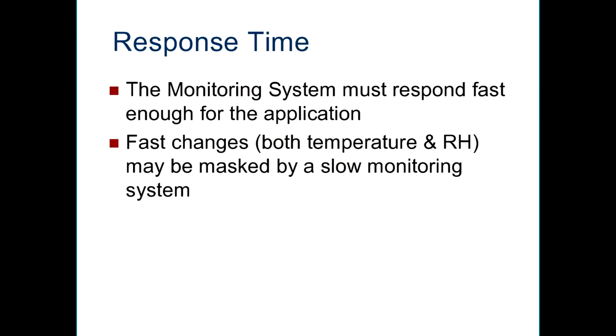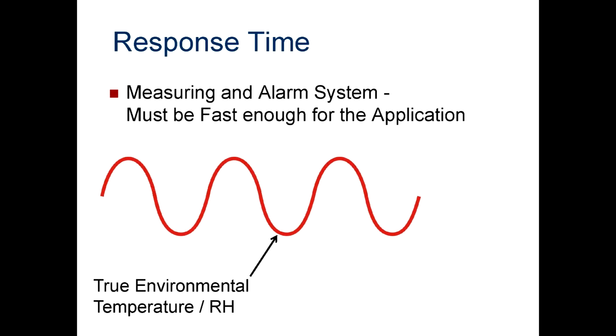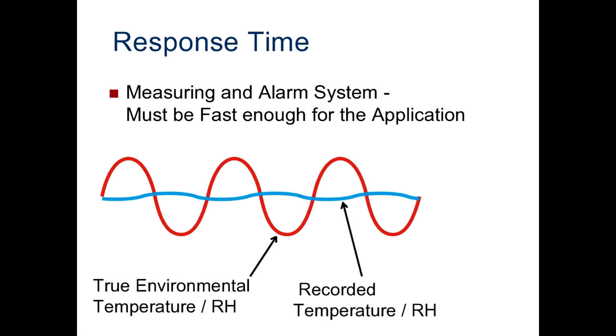Another parameter to keep in mind in a monitoring system is the response time. The monitoring system must respond fast enough for a given application. A high rate of change and a material or process that's very sensitive, if you don't have an appropriately fast monitoring system, you could miss the change and potentially get into trouble because you don't see it. In this example, we have shown on this red line the true environment, the true swings that may be going on in an environment, both temperature and relative humidity. Now, that's fine, but if we have a measuring system that's quite slow and an alarming system that goes with it, it may not see those excursions.